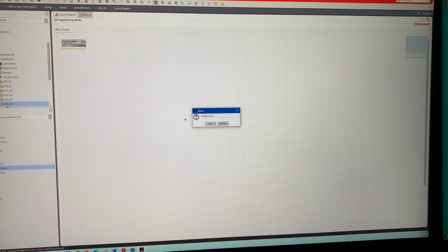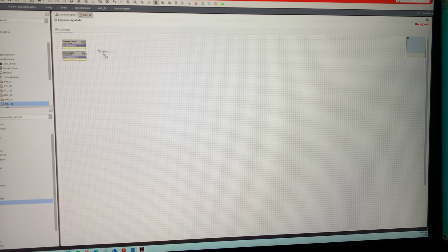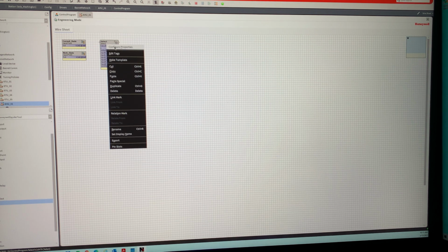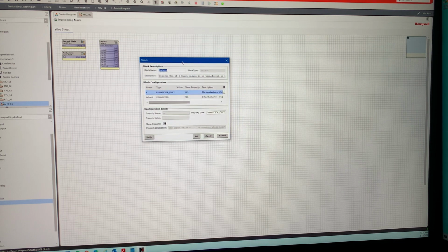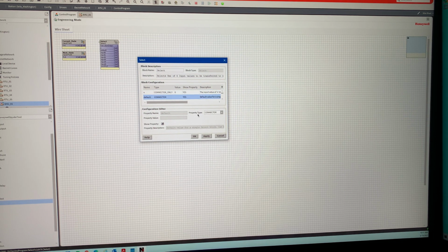our next state, which if you ever want to get into building optimization, that's where this really comes in handy. So we're going to take our select block, and this is going to be for occupancy. So we'll go to configure properties. I'll bring this over here. Our default, make that a constant. I want our default to be occupied just in case for some reason something happens with the program. It knows that, let's go ahead and stay occupied.